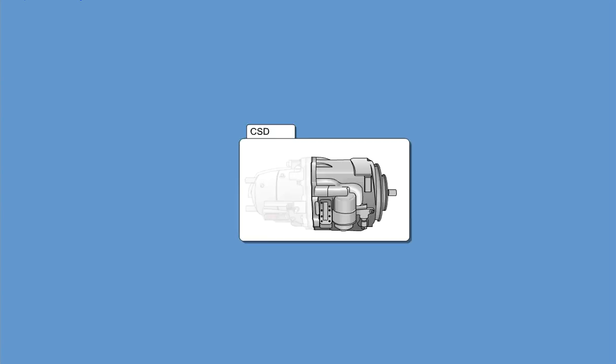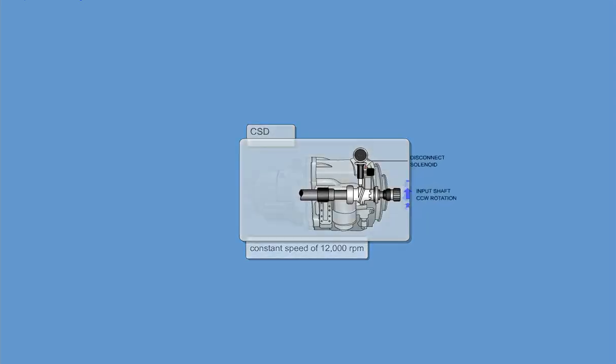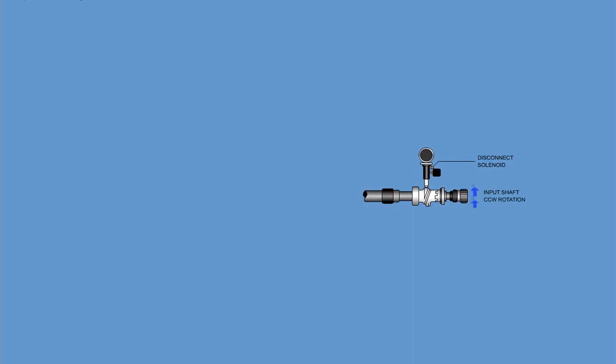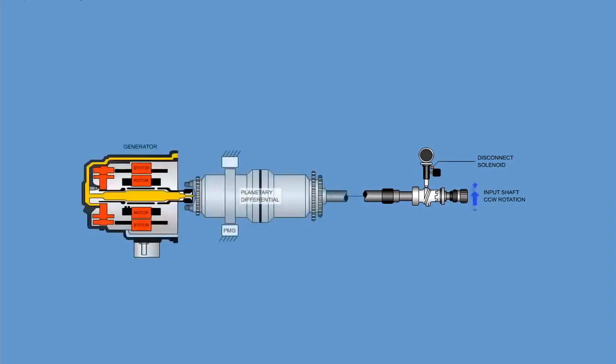The constant speed drive enables the generator to operate at a constant speed of 12,000 RPM, regardless of the variable engine speed and generator load. The input shaft of the CSD drives the generator through a 1:2 ratio gearing and a planetary differential gear. As long as the input drive shaft is at 6,000 RPM, the generator operates at 12,000 RPM and produces 400 Hz. When the input shaft rotation speed varies, the generator frequency also varies.